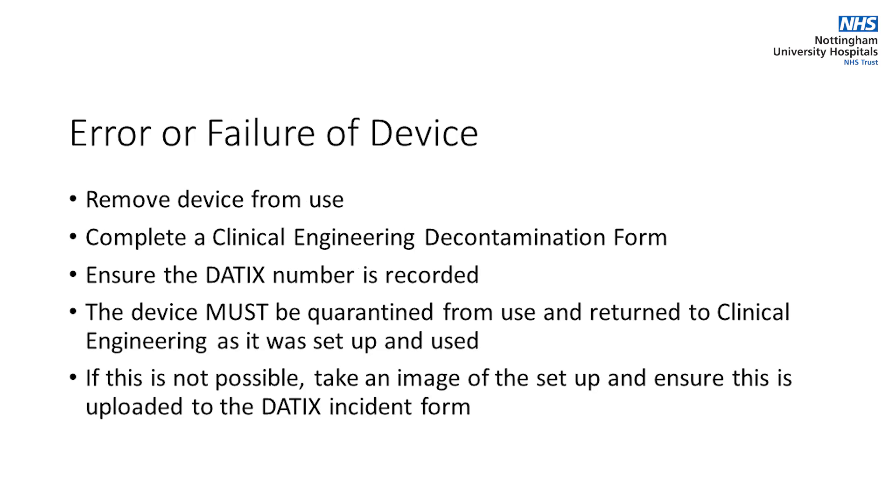If there is an error or failure, remove the device from use after ensuring the patient is safe and unharmed. Complete a clinical engineering decontamination form detailing any error codes or messages. If the device is involved in an incident, ensure the DATIX number is recorded on the decontamination form. Ideally, return the device to clinical engineering as it was set up and used. If this is not possible, please take an image of the setup and ensure this is uploaded to the DATIX incident form.